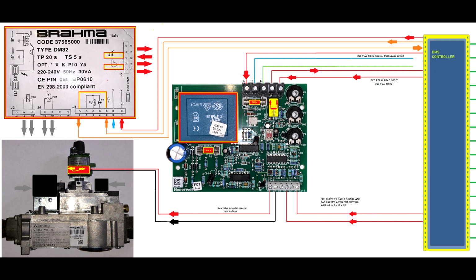So if the system is healthy, then the Brahma controller will jump to the next sequence. It will enable the ignition. You have a spark plug with a very high voltage that will create an electrical discharge, like a flash in the sky, and then automatically the gas valve will be enabled. The gas will pass through this ignition, this electrical voltage discharge, and will be ignited, and then you'll have a flame. While you have that flame, there is a flame monitoring device. It could be an ionization probe, a UV probe, it could be any type of probe, but in the Brahma controller's case it is an ionization probe.